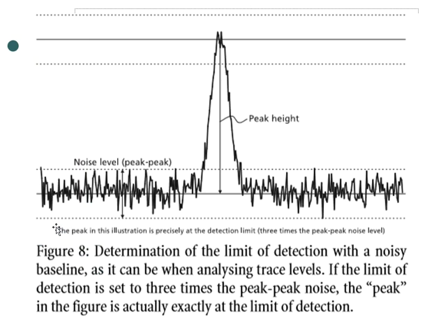All right, so here's an example of what we're talking about. If you zoom in on your baseline, what you'll see is that this constant noise will go up and down, up and down as the instrument is running. Well, if you zoom out enough, you're going to see a flat baseline, but it actually isn't flat, folks. It really isn't. If you zoom in enough, you're going to see this constant up and down, what we call noise, that's happening from the baseline. And then all of a sudden, an ion comes out, bing, and then it comes back down, right? And we want to make sure that this height is going to stand out from the crowd, meaning the baseline down here at the bottom.